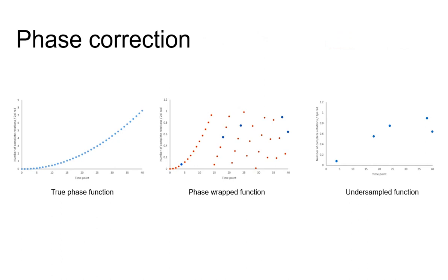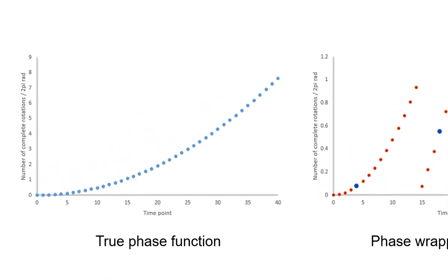The difficult part of the process of producing an absorption mode FTMS spectrum is correcting for the different phase angles associated with ions oscillating at different frequencies. In both ICR and Orbitrap class mass spectrometers there's an algebraic relationship between the ion oscillation frequency and its phase angle, and therefore if we can solve for the function that describes that relationship, we can correct for the phase shift seen in the ion signals, and that's what allows us to produce an absorption mode spectrum.